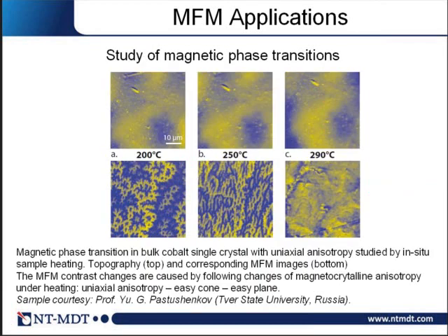It is also interesting to perform MFM at different temperatures to investigate magnetic phase transitions. Here you see MFM images made on bulk cobalt single crystal at different temperatures. The topography shows no changes with temperature, but the changes in MFM images are dramatic. By analyzing these images one can conclude that the magnetic crystalline anisotropy is changing as the sample is heated — from uniaxial to easy-cone or easy-plane anisotropy — and you can detect this using MFM.